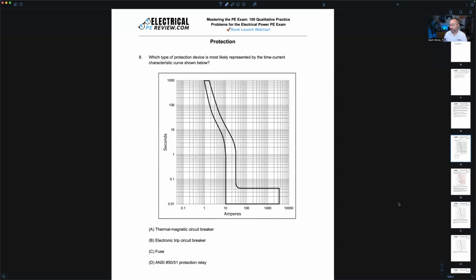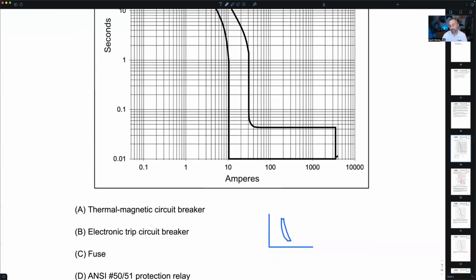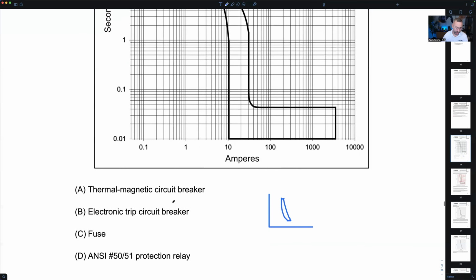Correct. What does a fuse typically look like? And I've got it coming up. But a fuse is kind of typically just like this, more or less, depending on if it's current limiting or not, but we're definitely not going to have this instantaneous trip section, right? It's really just a sliver curved area. So it's not a fuse. So I would eliminate that one right off the bat. All right, ready for the answer? The answer is A. This is a thermal magnetic circuit breaker.